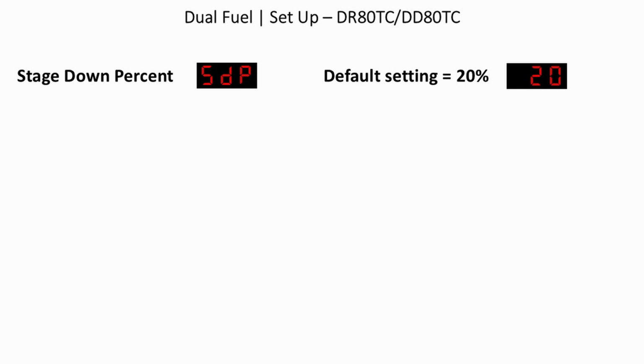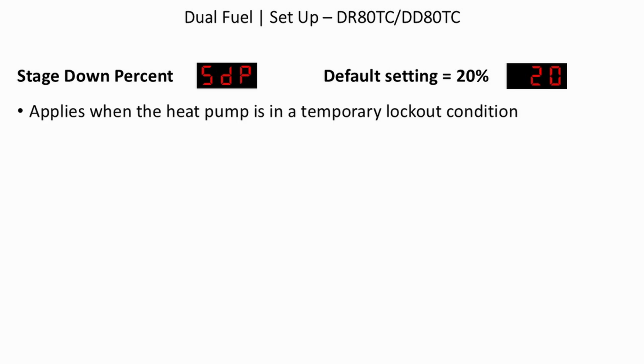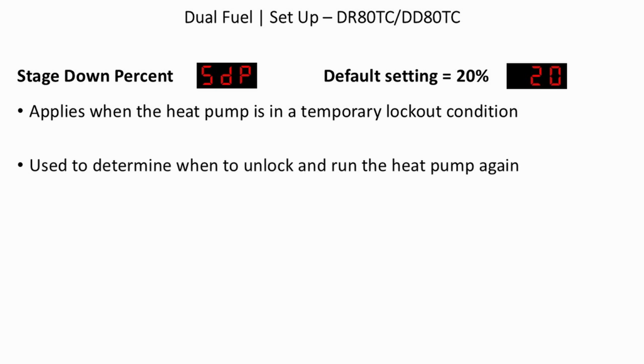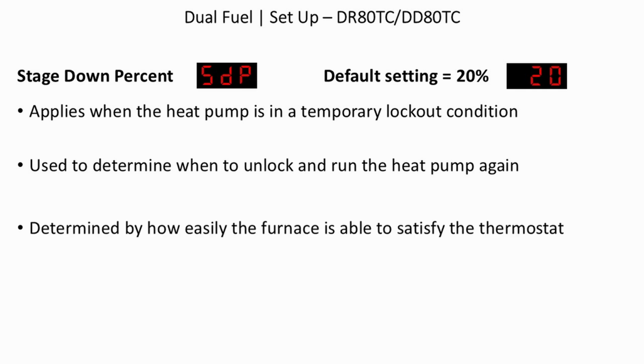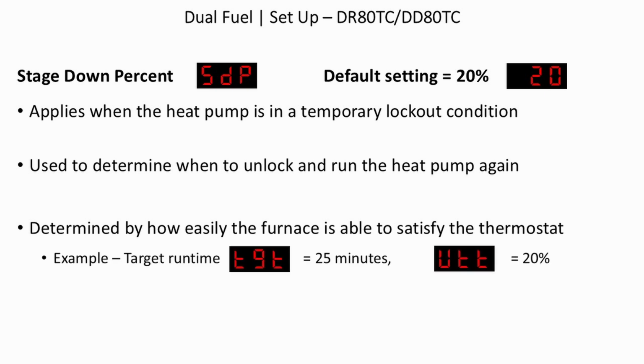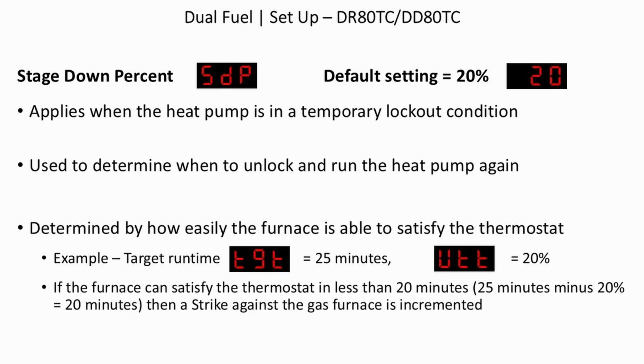Stage down percentage, SDP. Default setting, 20%. This applies when the heat pump is in a temporary lockout condition. It is used to determine when to unlock and run the heat pump again. It's determined by how easily the furnace is able to satisfy the thermostat. For example, if the target runtime, TGT, is 25 minutes, the UTT is 20%. If the furnace can satisfy the thermostat in less than 20 minutes, that's 25 minutes minus 20% is 20 minutes, then a strike against the gas furnace is incremented.